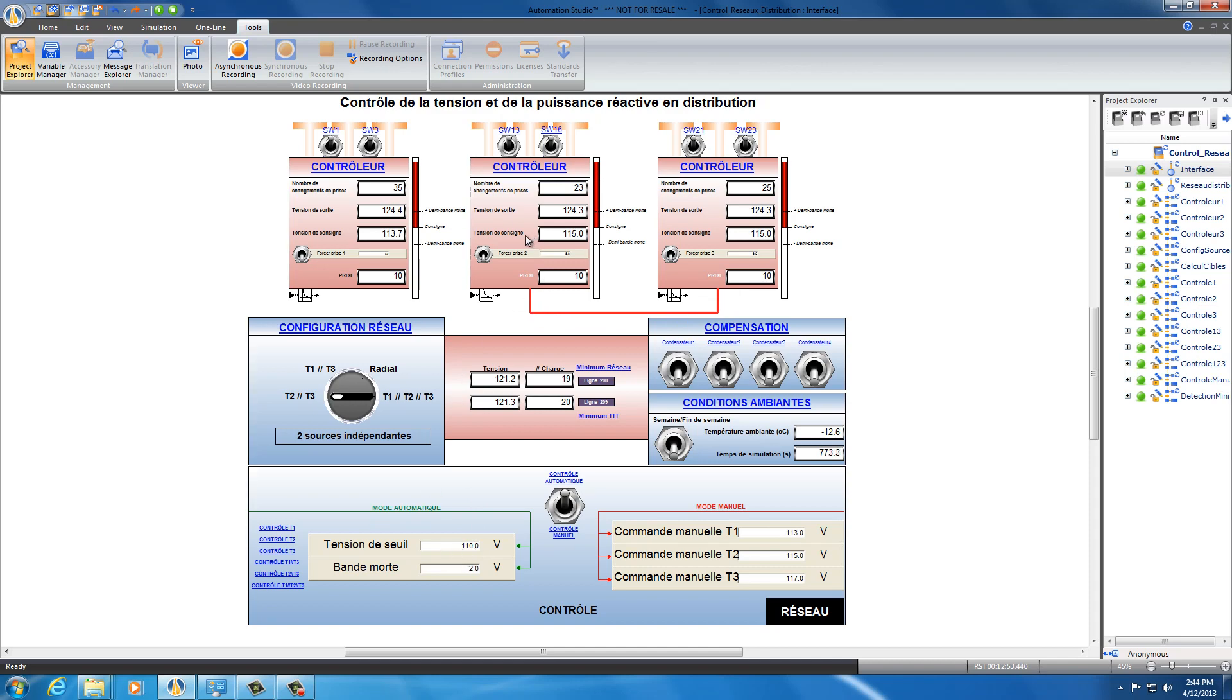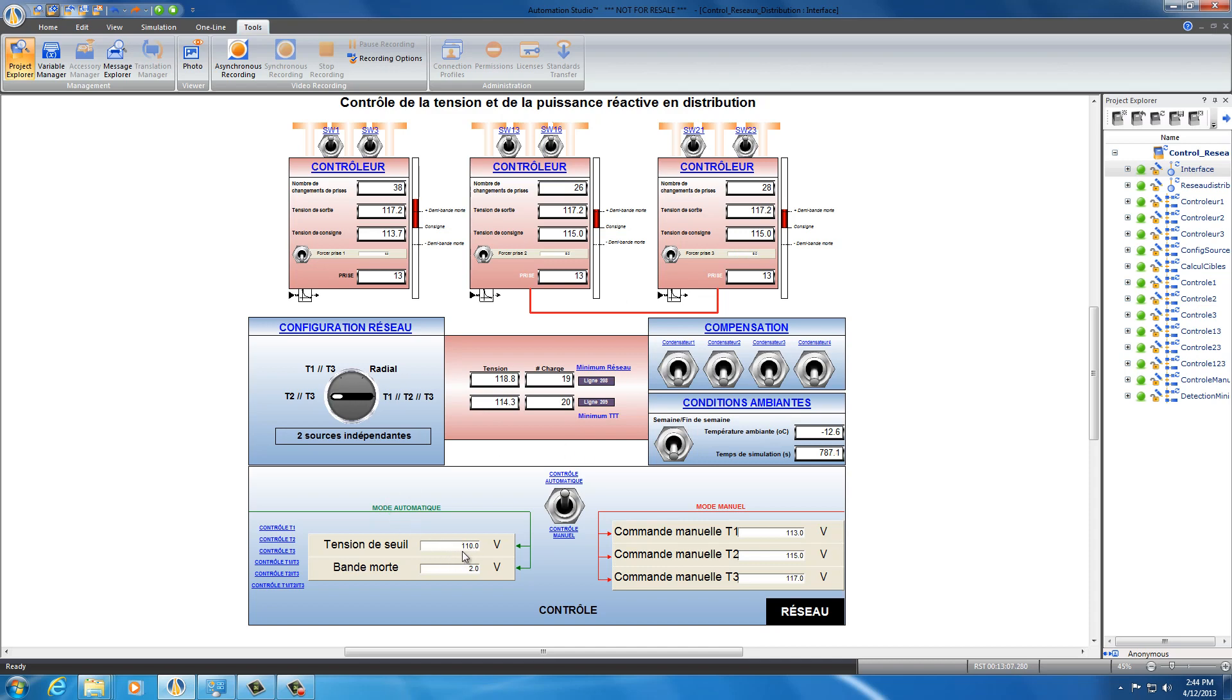It's going to adjust the output voltage in accordance to this one to put this 110 volts. So here now it arranged itself to 115 at the output of the transformer. So transformer 2 and 3 have to have 115 as an output voltage so we get the minimum voltage here of 110. Let's do another one.